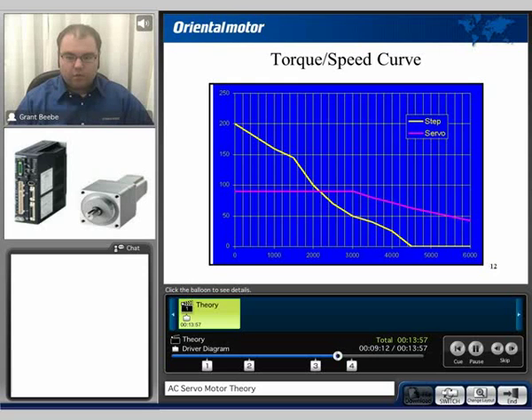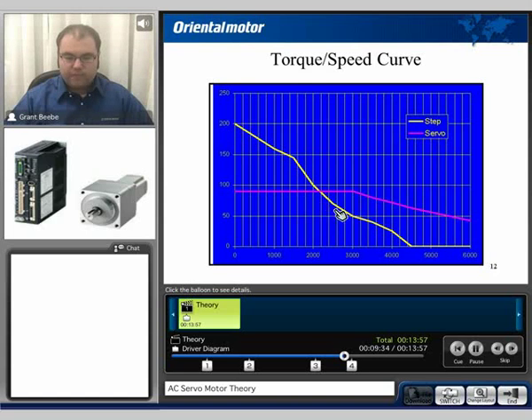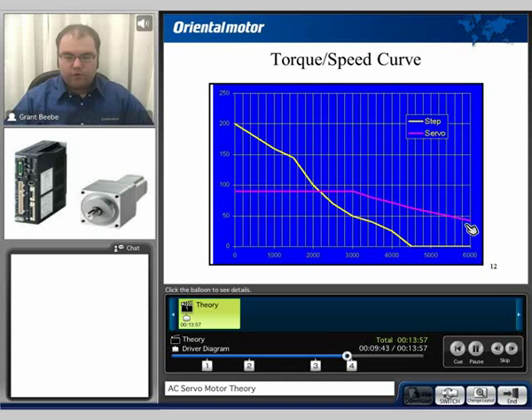Here's a torque-speed curve showing the actual performance output from a servomotor. The servomotor line, which is in pink, is relatively flat up to about the 3,000 to 3,500 rpm range and then begins to drop down. Similar to that of a step motor — we can see that the step motor has a much higher starting torque, but as the speed increases the torque drops down approaching the 2,500 to 4,000 rpm range. There's not much usable torque after that for the step motor, whereas we can see we still have usable torque with the servomotor.